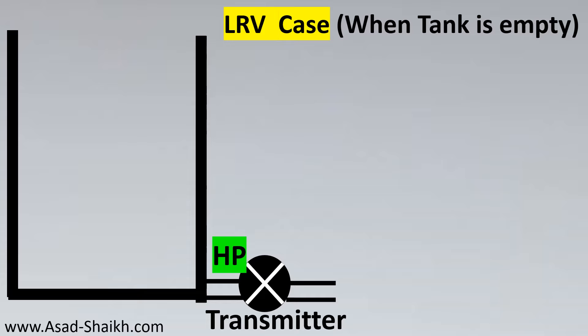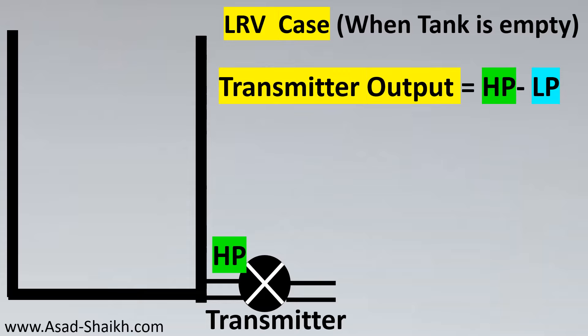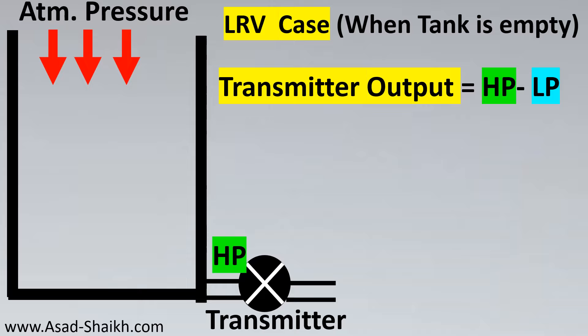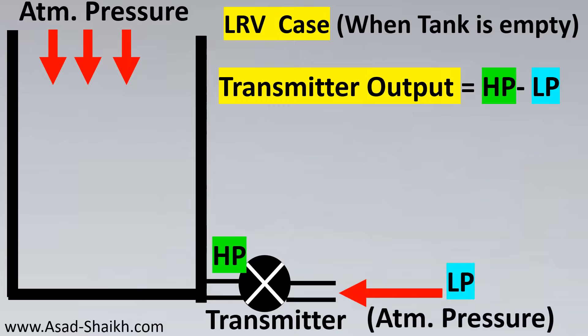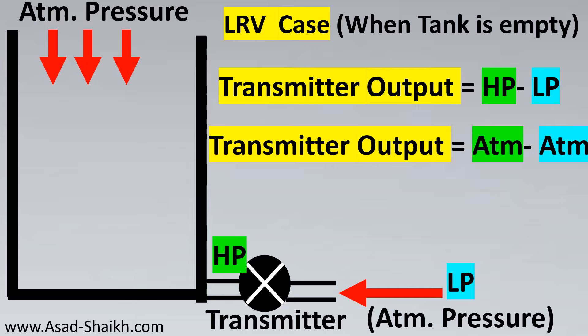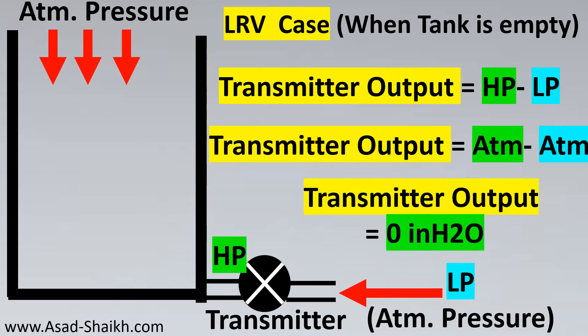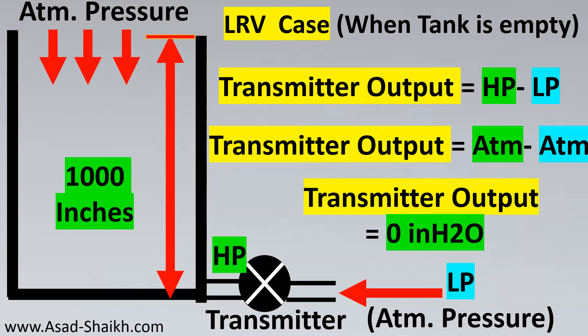Now let's look at the LRV case when the tank is empty. The transmitter output is HP minus LP. Since the tank is open to atmosphere, atmospheric pressure acts on the HP side, and the LP side is also open to atmosphere — so both sides only have atmospheric pressure acting. The transmitter output is therefore 0 inches of H2O. Even though the C-to-C distance is 1000 inches, there is no liquid in the tank, so no head is acting on the HP side.